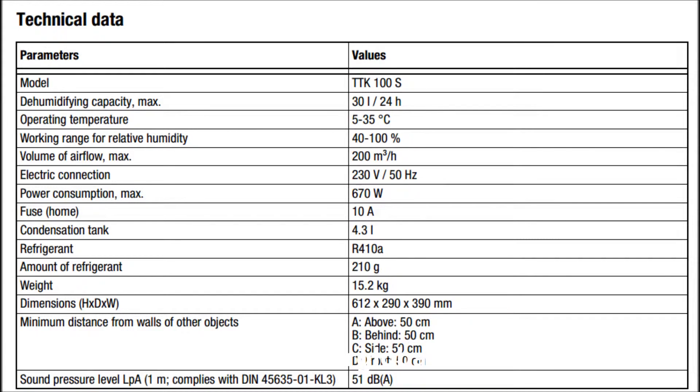The technical data of model TTK100S are: dehumidifying capacity max 30 liters per day, operating temperature 5 to 35 degrees C, working range for relative humidity 40 to 100%, volume of airflow max 200 cubic meters per hour, electric connection 230 volt, power consumption max 670 watts.